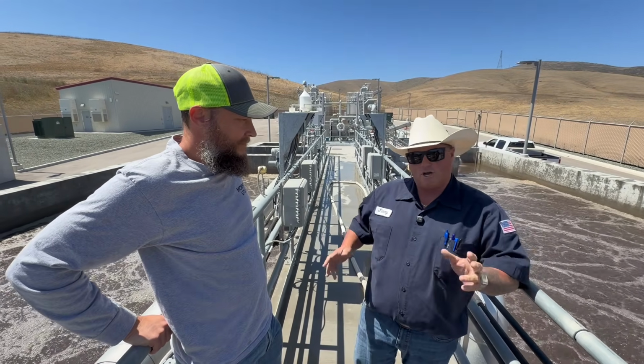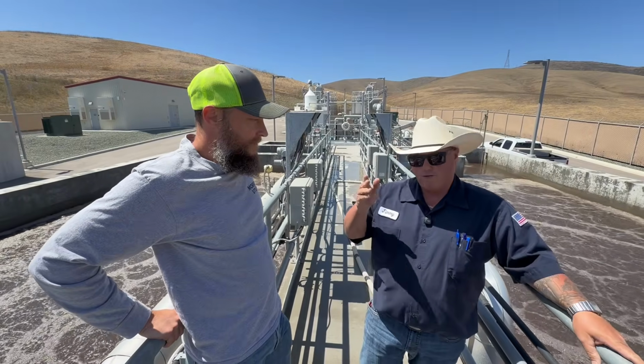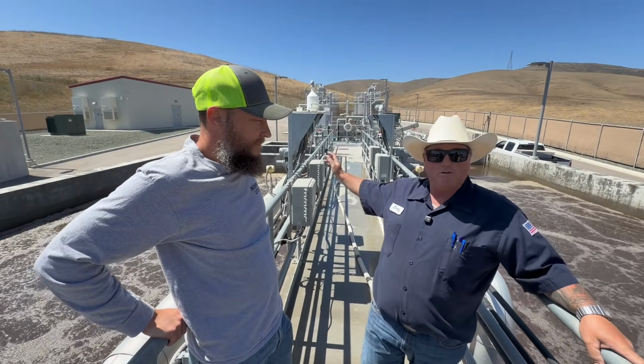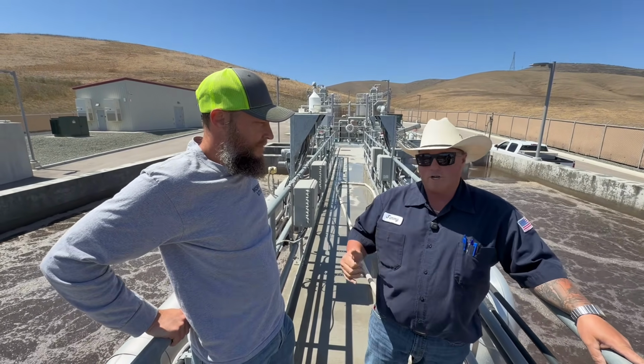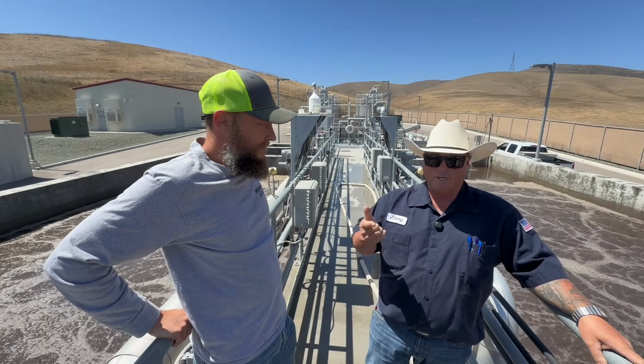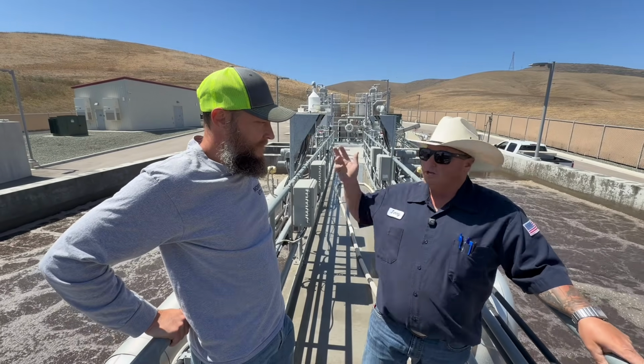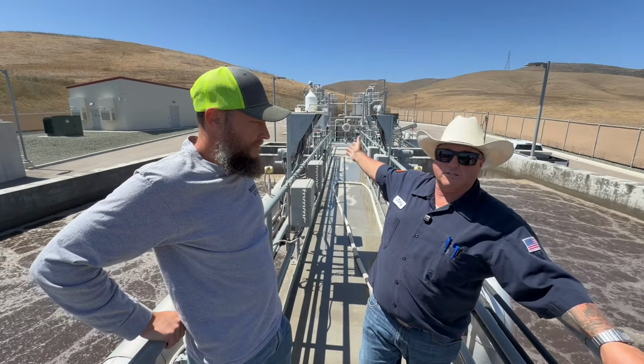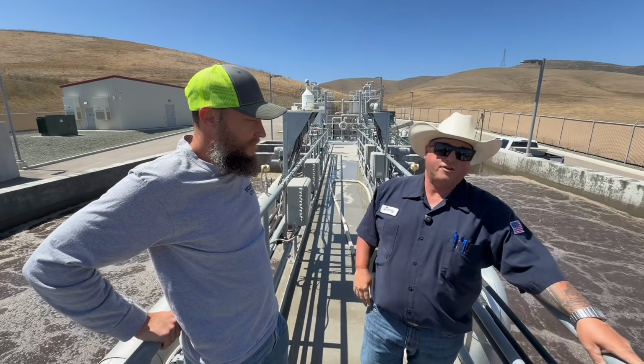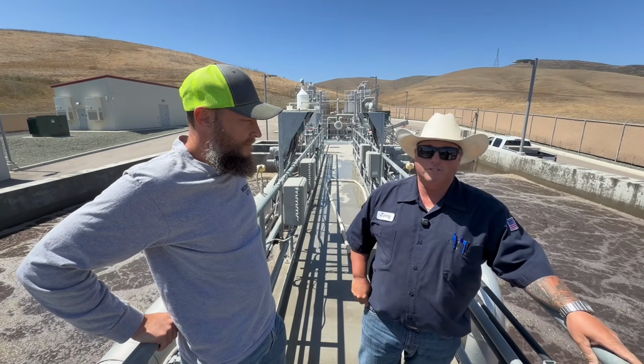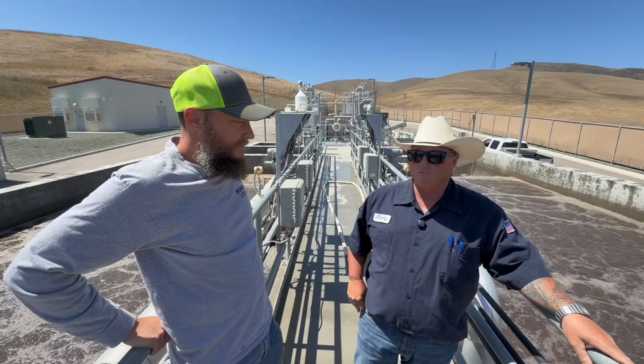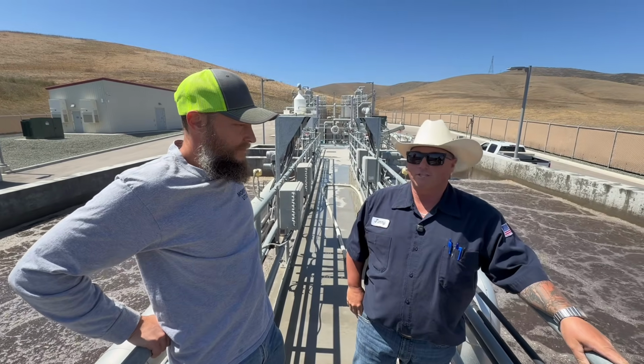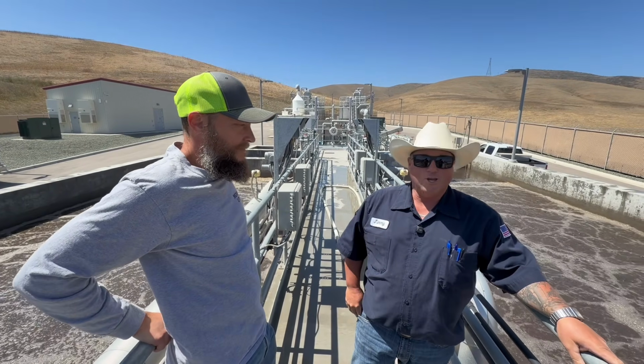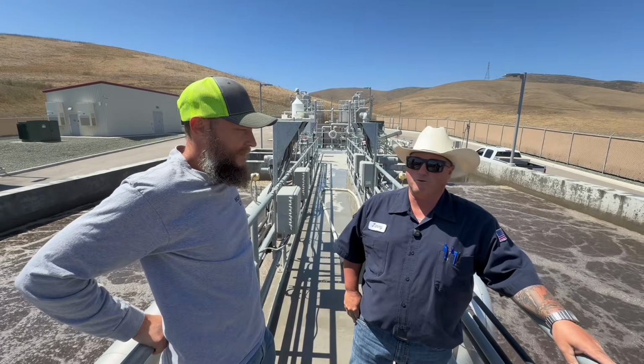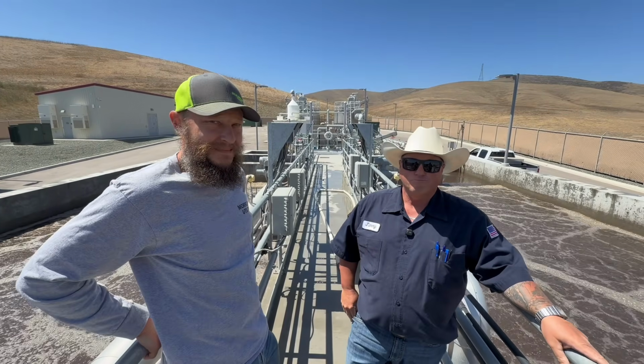These probes talk directly to SCADA via 4-20 or millivolt signal. They tell the plant what it needs as far as more air, less air, more pH. To keep the pH balanced, we need alkalinity in the denitrification. Without these components, and with us being able to see it at all times, you don't have denitrification, and you won't have nitrification, and you're not going to process your wastewater very well. You're going to blow your permit.